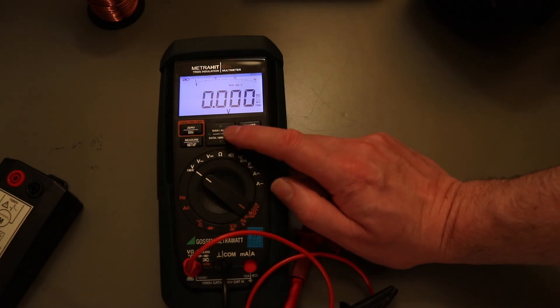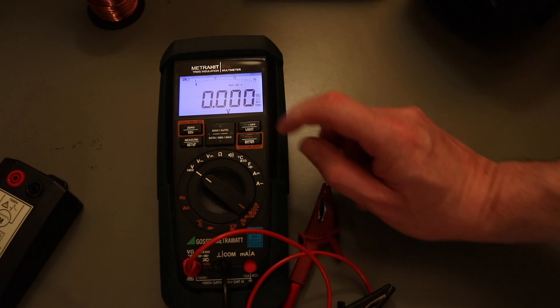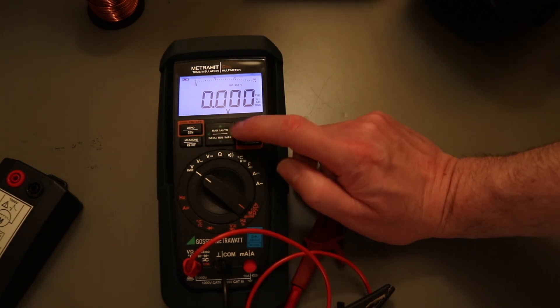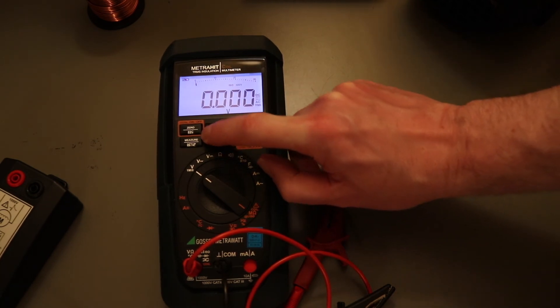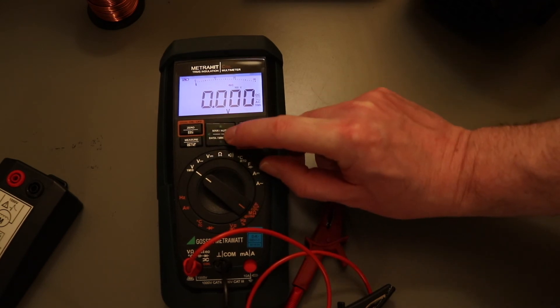The other problem I've had with this is that whilst you can go and swap the voltage through the menu system, you can also use this function button in the middle here for the side functions. If you watch the 250 volts up there, it changes through to 500. But that's not cycled through. And you have to take it either way. And what I found myself doing, sometimes when I slightly mishit that, I alter the voltage.